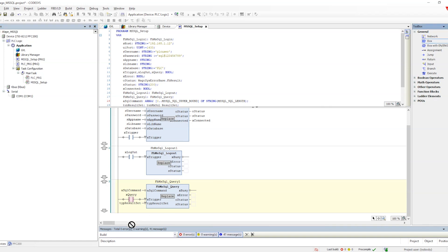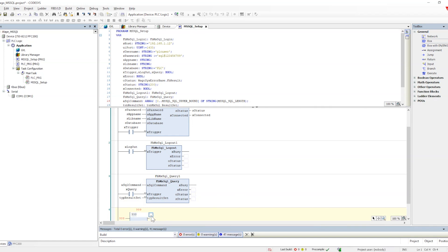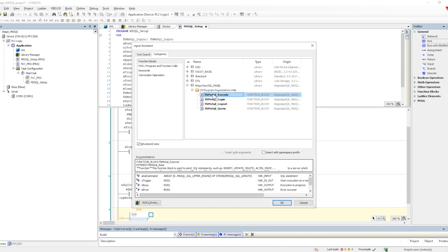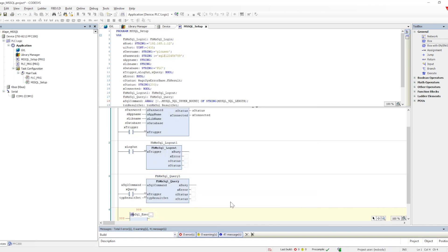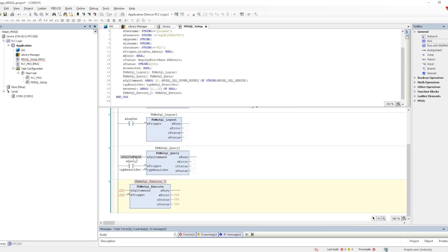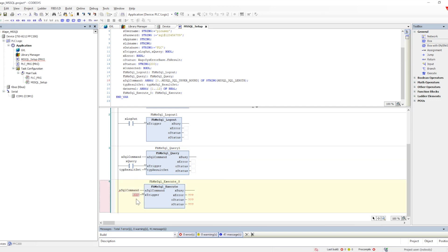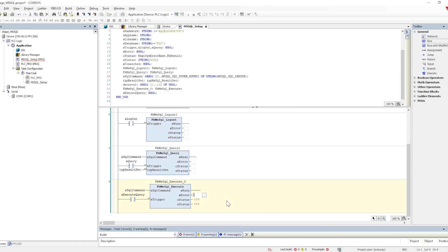Now let's look at another function block through which we can insert, update, or append data into the database — FB MS SQL Execute. The execute function block is utilized for different purposes: the query block is only for SELECT, while execute is used to write or update anything into the database. It has the SQL command input but does not have a response/receive part, since we are writing data rather than reading it.